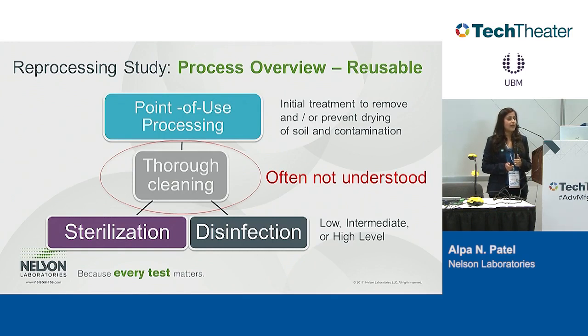often misunderstood. And the reason for this is because these validations seem to be grouped together with sterilization or disinfection, and usually people think it's a decontamination validation where we're grouping everything together as it's proposed or as it happens in the healthcare facility. When you go to the healthcare facility, you start with cleaning or disinfection and sterilization. There it's understood that it's done as one process. But if you do validations, we're doing it in all different steps. And depending on how your devices are used is how they would be tested.